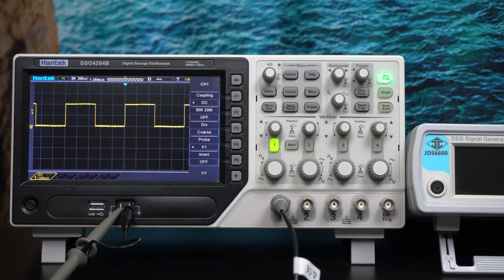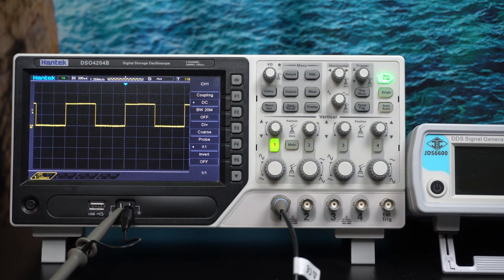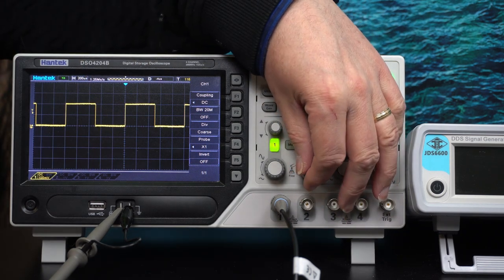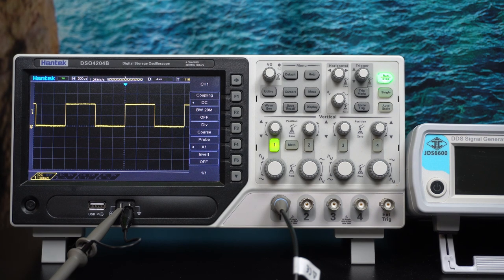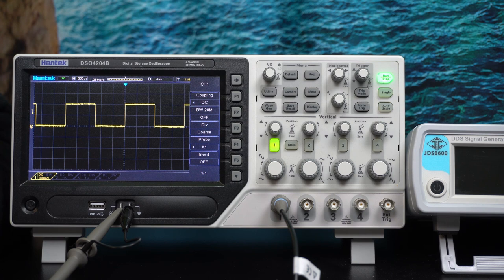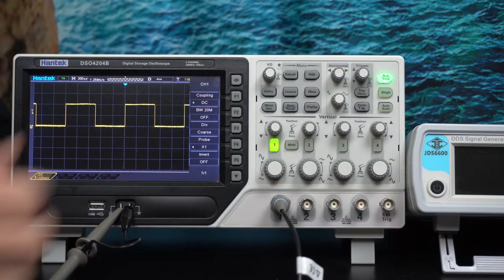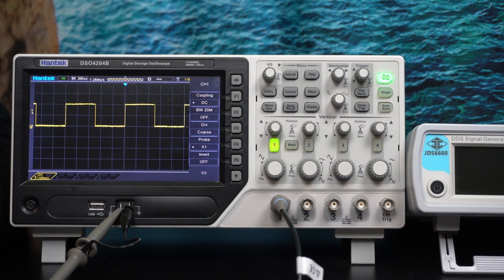People try to present oscilloscopes as incredibly complicated devices, and yes, they are if you're using the very advanced features — but this is absolute basic usage. Do the mental exercise: it's got a lot of buttons, but say 'okay, what do I actually need?' Switch off everything you don't need, and make sure you return the oscilloscope to its default mode. If you come to an oscilloscope with four channels connected to a random circuit doing all sorts of analysis, disconnect all the probes and start from the basics. Learning each oscilloscope is a stepwise activity — start with one channel, one probe, and begin with probe calibration.